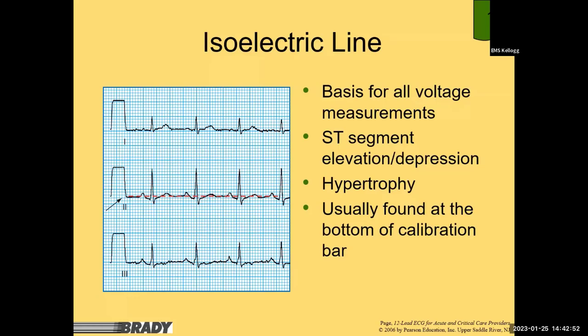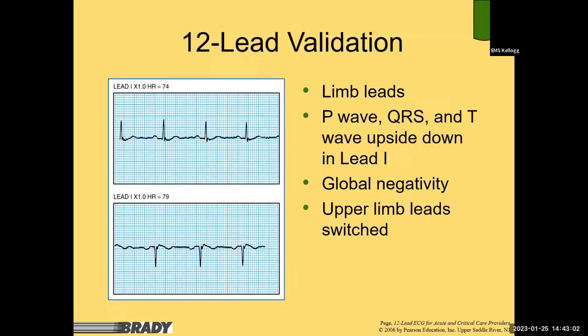You can see the calibration bar where it bottoms out repeatedly — that boxy section at the beginning of the strip. To validate your 12-lead, make sure leads are properly placed — limb leads should go on the limbs.